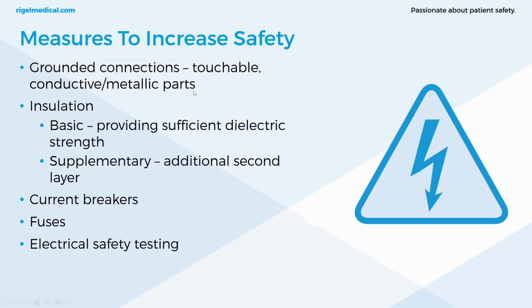So there are several specified mandatory barriers within the circuitry of medical devices to guarantee that leakage currents are non-hazardous. One of the main ones is a grounded connection. Now this is not true for all devices, this is only for class 1 devices, and it relies on a protective earth which provides a very low resistance earth path for leakage currents to flow to ground if anyone was to come in contact with exposed conductive parts. So if a fault was to occur and there was a large current on the enclosure, it will follow that easy secondary earth path back to ground rather than through the patient or the user. On top of this, the surge in current down the earth or ground will be detected by RCDs, protective fuses, which will interrupt the voltage supply.